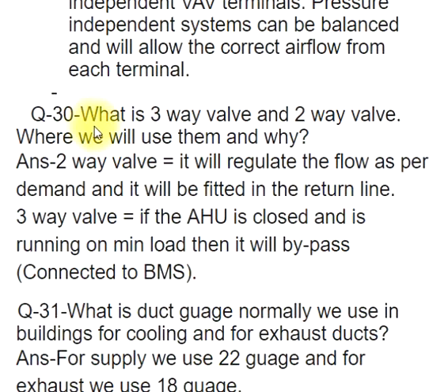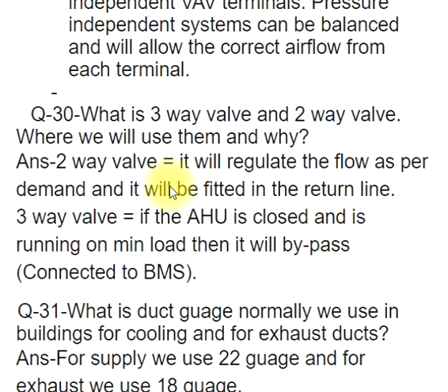Q30: What is a 3-way valve and 2-way valve? Where and why do we use them? ANS: 2-way valve regulates the flow as per demand and is fitted in the return line. 3-way valve: if the AHU is closed and is running on minimum load then it will bypass; connected to BMS.